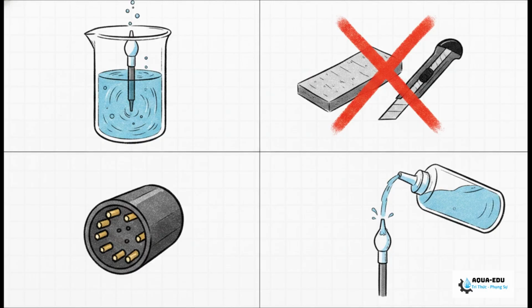But listen, this is absolutely critical. Never, ever use sandpaper or any sharp object on that platinum surface. You'll ruin it. Just check that your cable connectors are totally dry and free of any oxidation, and then always finish your prep with a really thorough DI water rinse.